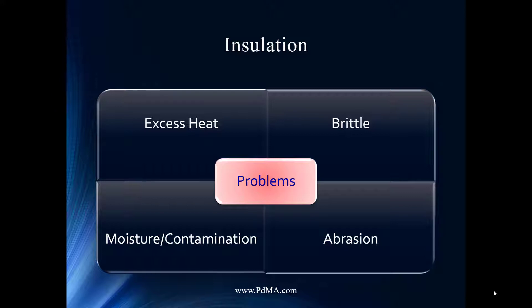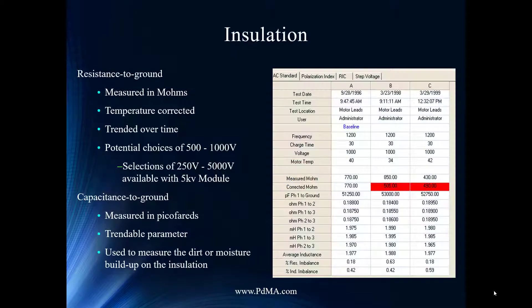A helpful way to remember insulation class temperatures: Class A starts at 105°C. Just add 25 degrees for each subsequent class. So the steps are 105, 130, 155, and 180°C. Now, when we look at insulation testing, our standard test measures in megaohms and we temperature correct — why do we do that?